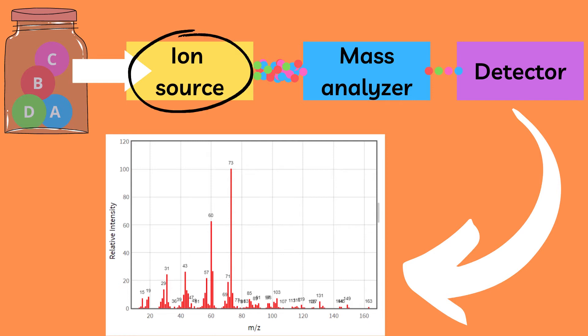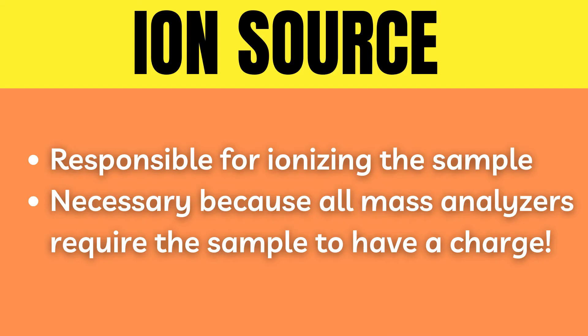The ionization source, as the name suggests, is responsible for ionizing the sample. This is necessary because all mass analyzers utilize the interaction between an electric field and the ionized sample — therefore the sample requires a charge in order for the mass analyzer to do its job.